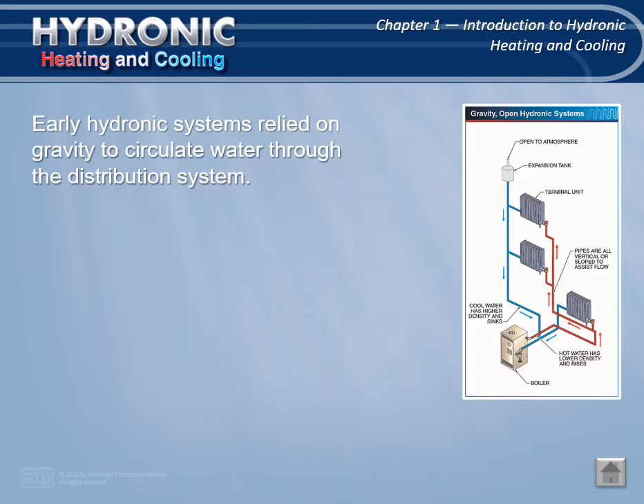We will be discussing some different types of hydronic heating systems. A gravity hydronic system is a hydronic system in which circulation to the heating units is accomplished by the difference in density of water in the supply and return mains. As we can see on the diagram, the hot water has a lower density and rises as it hits the terminal units and it gives off its heat. The cool water has a higher density and sinks back into the boiler. As you can see on top, the expansion tank is also there, which is open to atmosphere.